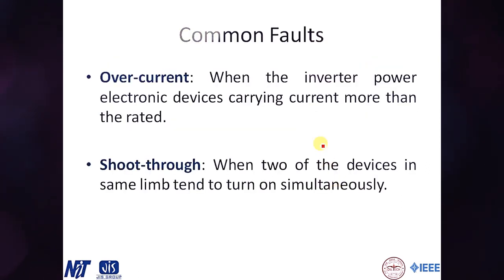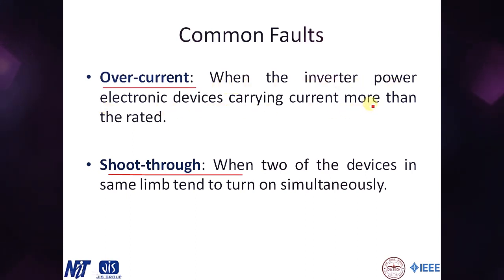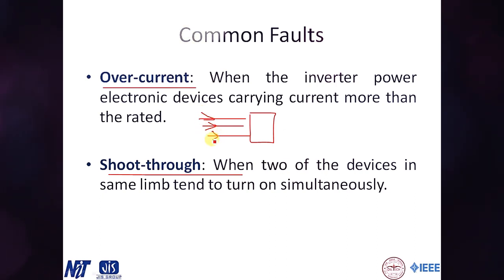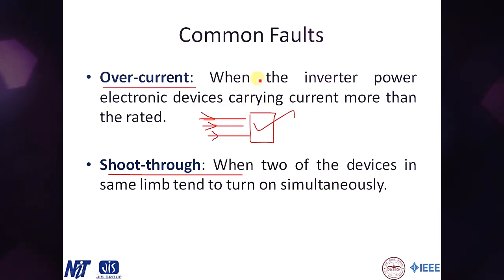Now, what faults are we talking about? The first is overcurrent — when the inverter's power electronic devices carry more current than rated. For example, a three-phase fault, phase-to-phase fault, or short circuit at the output will try to drag more current from the inverter. While relays protect connected loads like induction motors, the inverter itself has no inherent protection, so the IGBT will carry excessive current and eventually burn out due to thermal runaway.